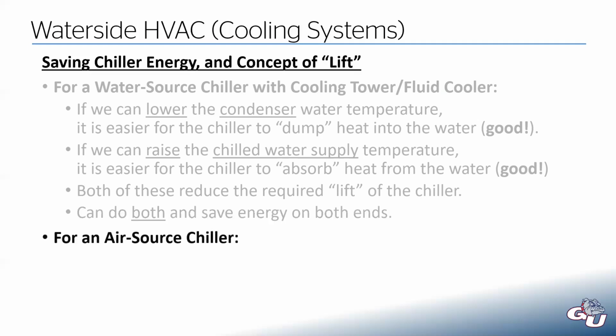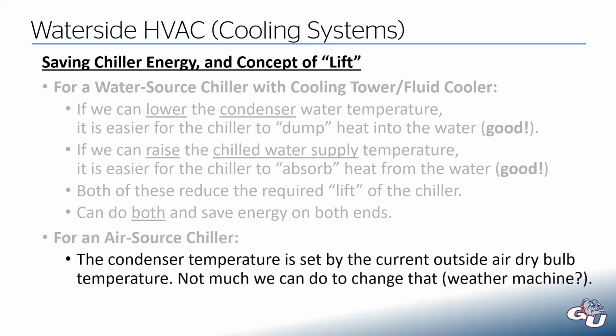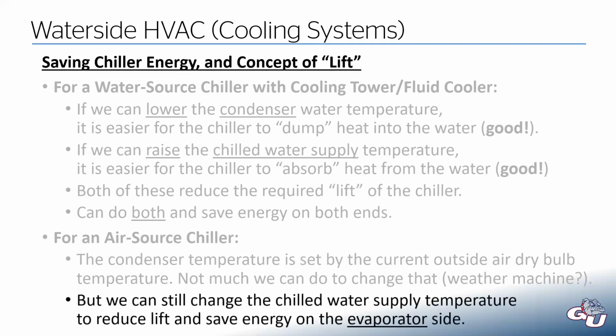For an air source chiller, the condenser temperature is set by the current outside air temperature. And there isn't much we can do to change that until we invent a weather machine. If it's 100 degrees outside, that is our condenser temperature on the refrigerant side, and we can't change that. Nothing we can do. But we still can change the chilled water supply temperature to reduce lift and save energy on the evaporator side. And I think I'll have some slides here that should help illustrate that.